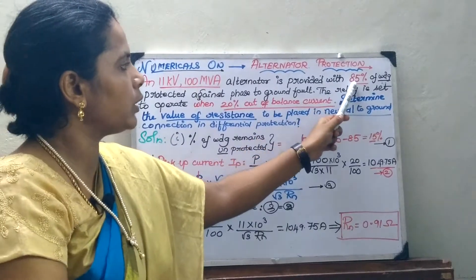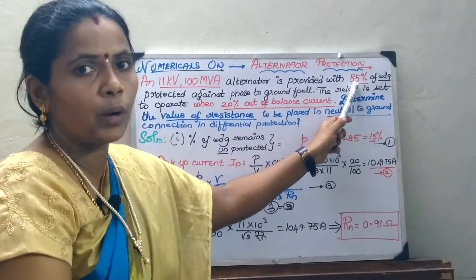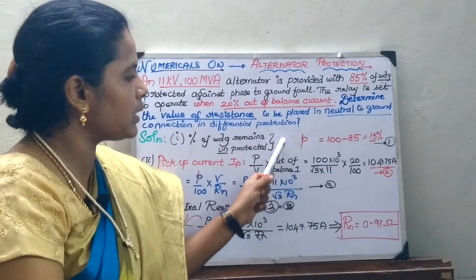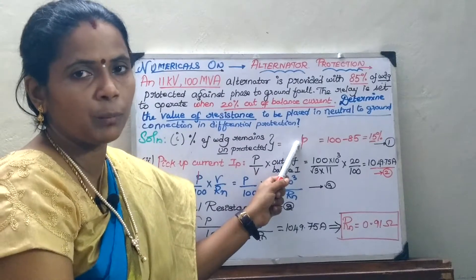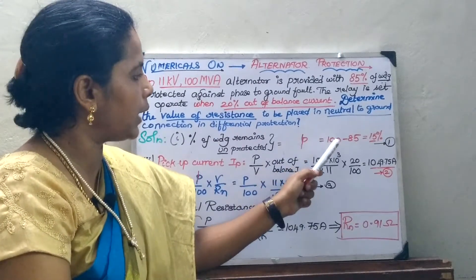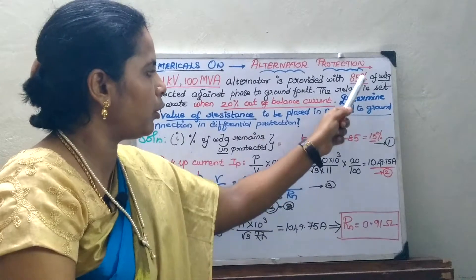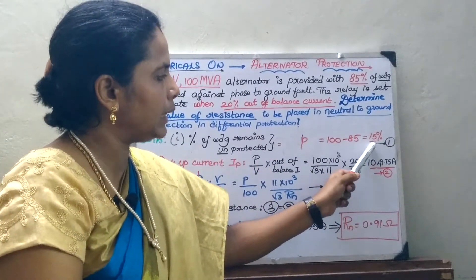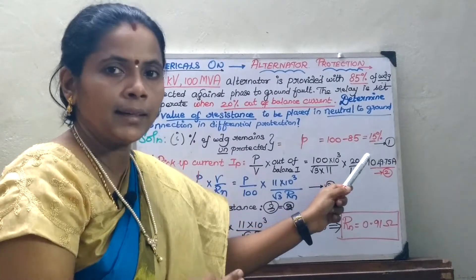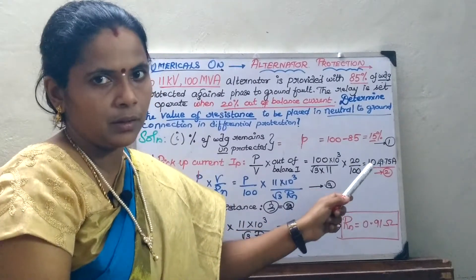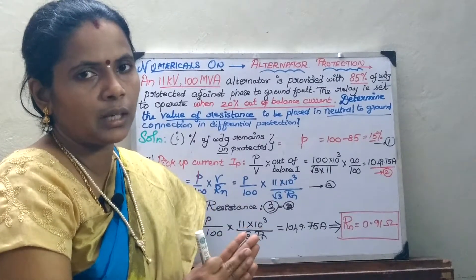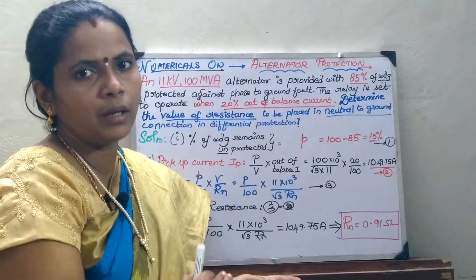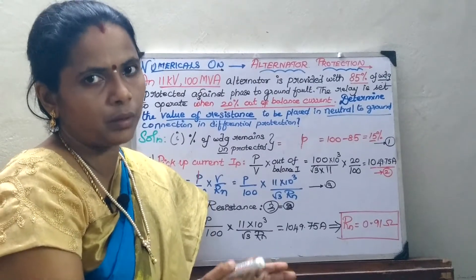The first thing: with 85 percentage of the winding protected, we need to find out the percentage of the winding that remains unprotected, specified by P. It is nothing but 100 minus however much of the winding remains protected. So 100 minus 85 gives 15 percentage of the winding that remains unprotected. Subtract the protected percentage from 100 to get the unprotected percentage.